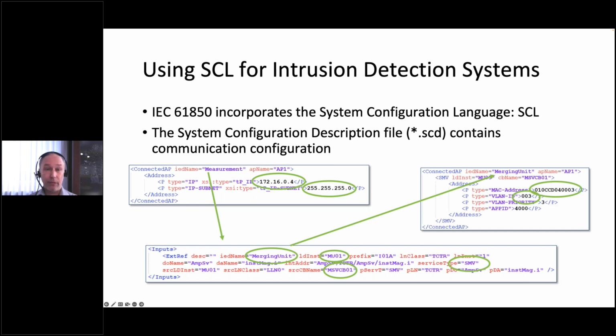Both from within the substation, but also from external sources. The examples shown here are from an SCD file. As you can see, there's a lot of communication parameters available that can be used by an intrusion detection system. For example, IP addresses of IEDs or virtual applications or destination MAC addresses used by sampled value publishers.